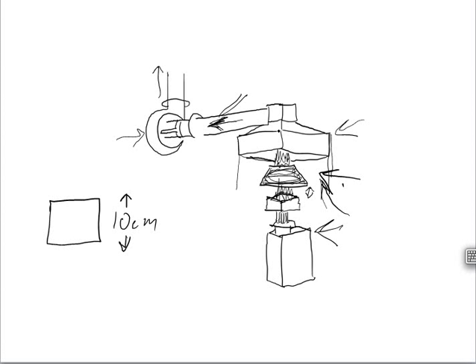What else was I going to say about this? So we have this electric coil. It goes up to a thousand degrees Celsius, and we can generate up to a hundred kilowatts per meter squared incident heat flux on the sample surface.